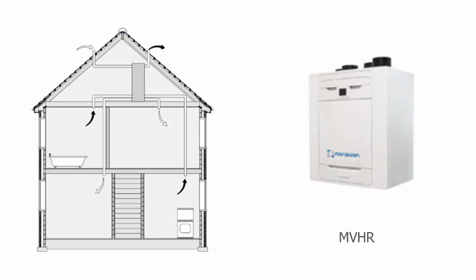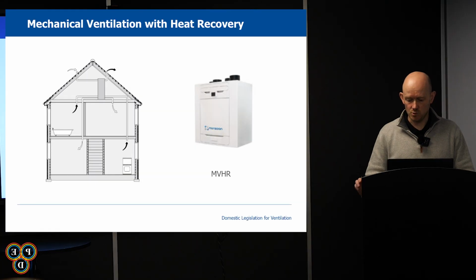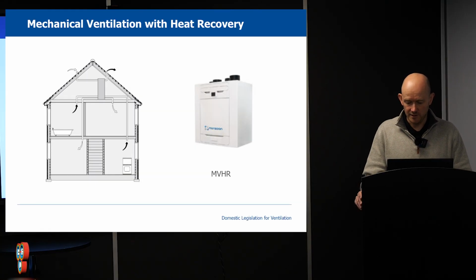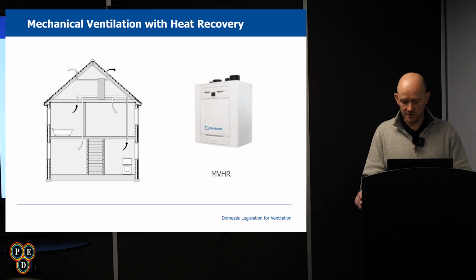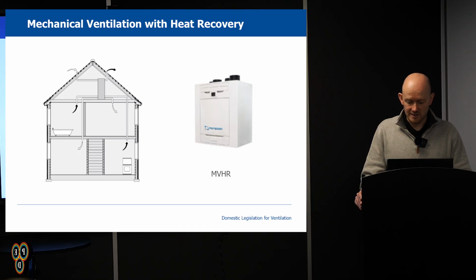MVHR is a whole dwelling ventilation system that supplies and extracts air continuously at a low rate, with the option to increase airflow rates for boost as and when we require. The unit is typically installed in a loft or a cupboard and connected into rigid ducting, which supplies fresh filtered air into habitable rooms and extracts stale polluted air from all the wet rooms. The unit incorporates a polymer heat exchanger that recovers energy from the stale, moist air and tempers the incoming air before it is delivered into the habitable rooms.